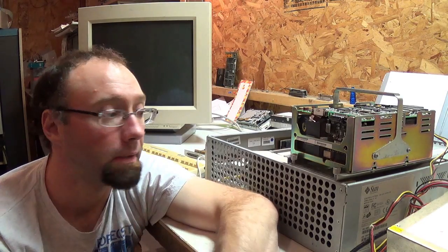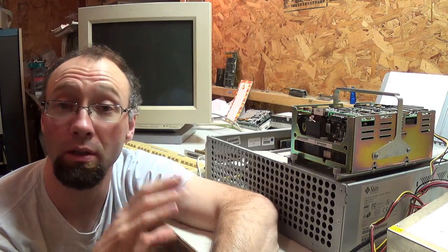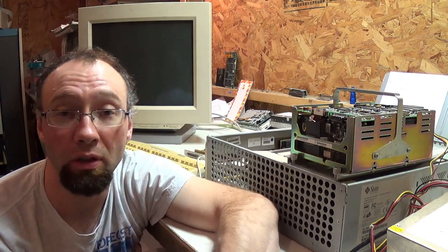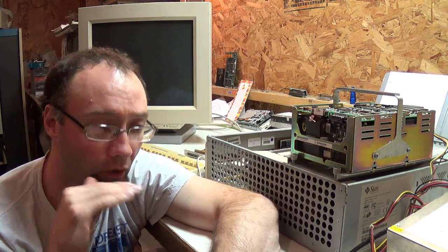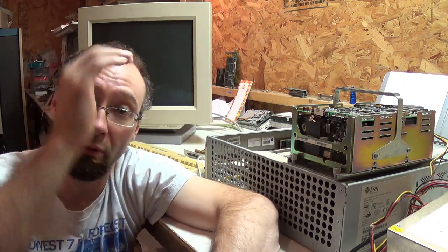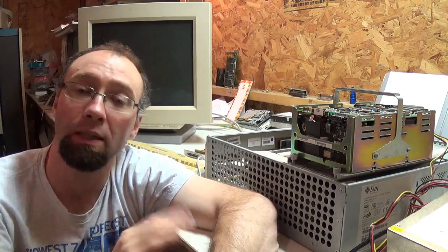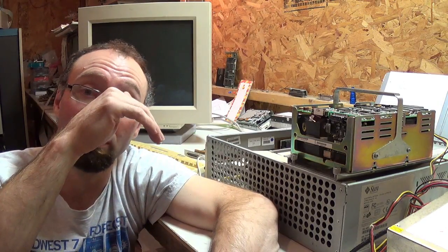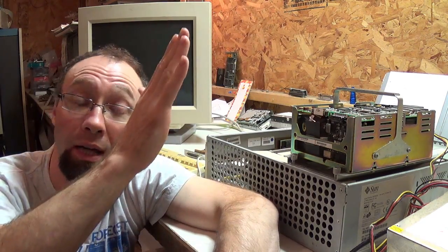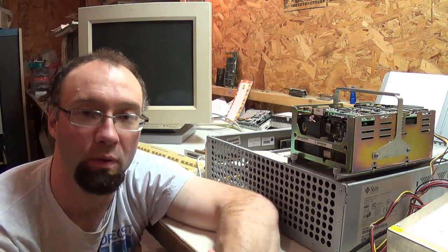And it's possible that what's going on with this is that the capacitors on the output stage are simply not doing their job properly anymore. Where they used to smooth out that voltage, that output, they're just not doing it, and so the voltage is doing this. Eventually it gets so bad that when the voltage is dropping, the power's failing, so it shuts the system down. Well, then it rebounds and starts ringing back up again. The system comes back up.